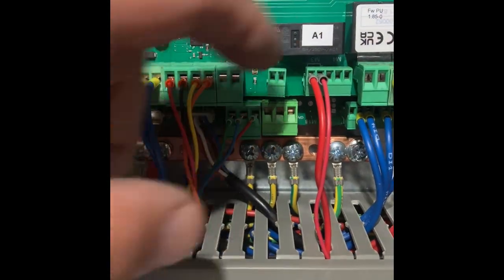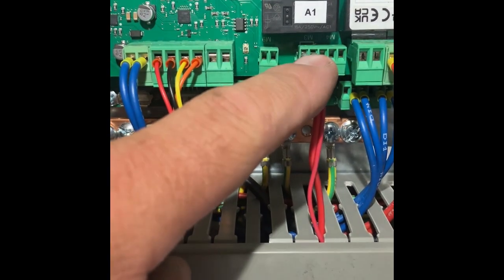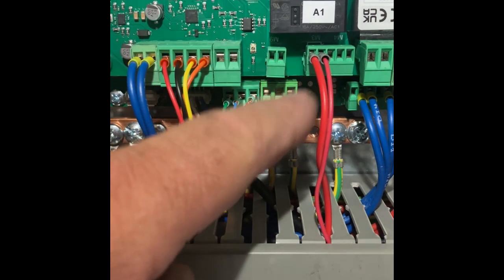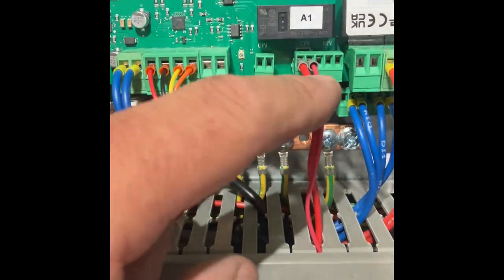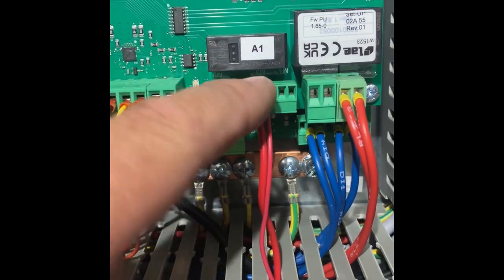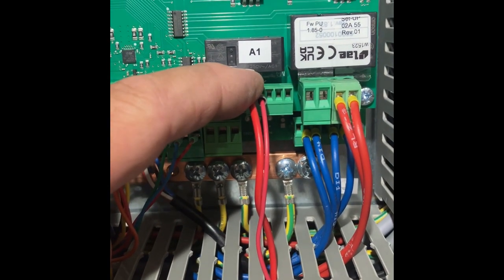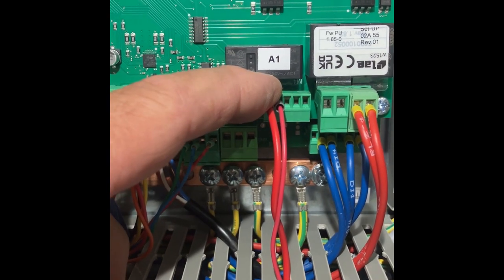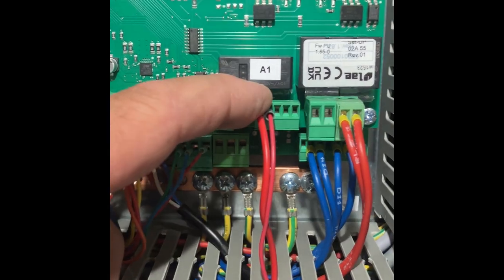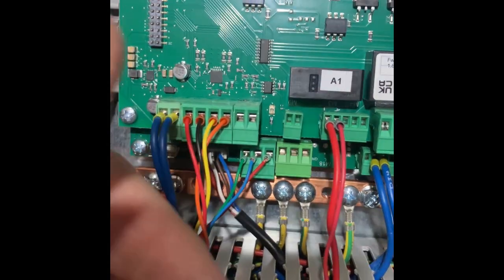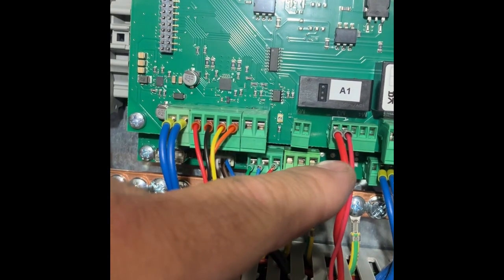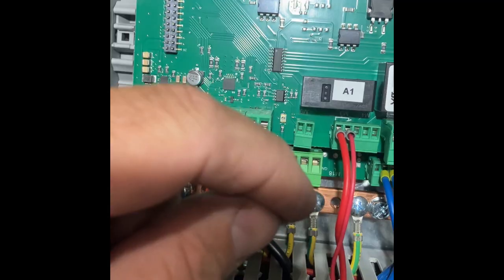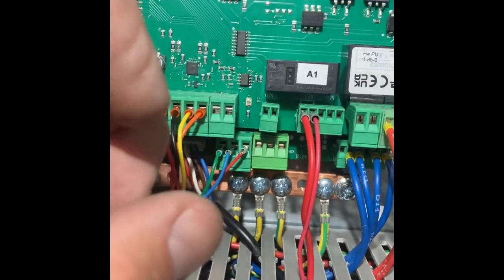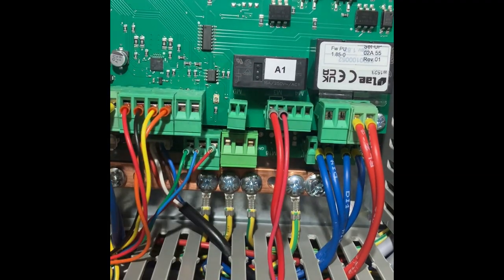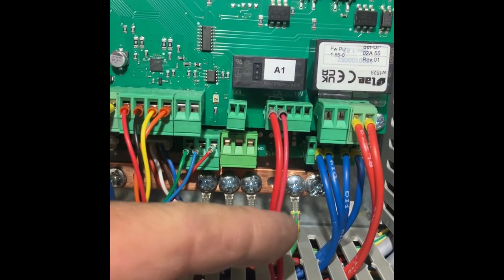Only other thing I want to mention on this, I'm actually tied into the normally closed alarm circuit, but it's open. And what I mean by that is right now, dryer is off. See, my drives are dead. Dryer is off. If I hit an ohm meter right now on these two terminals, I would get short circuit, right? No resistance, or very, very low resistance. But what happens is when the dryer kicks on, everything boots up, that contact changes state and opens up, and it will close again on fault. So even though it is technically the normally closed circuit, it operates like a normally open circuit, because when the controller boots up, it changes states.